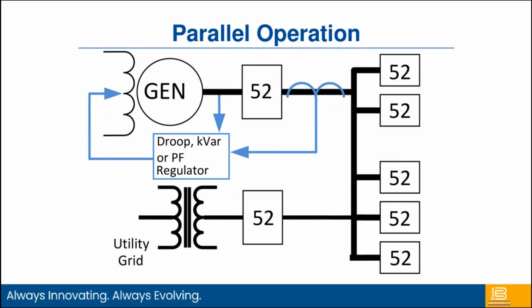Okay, so that's a little bit of background on how the voltage regulator works, but some of the advantages of digital voltage regulators is that now we have a microprocessor in the unit, so we can do a lot more calculations and do a lot more cool things with the voltage regulator. Primarily, we have a lot of customers that are going to parallel generators. When we parallel generators, we need to look at the current output because we need to be able to control, at a minimum, the VARs, the amount of reactive loading on that particular machine. So the voltage regulator controls the reactive power out of the machine. The prime mover, which is controlled by the governor, controls the real power, or the kW, out of the machine. So obviously, talking about voltage regulators, we're mainly concerned with that reactive component being output out of the machine.